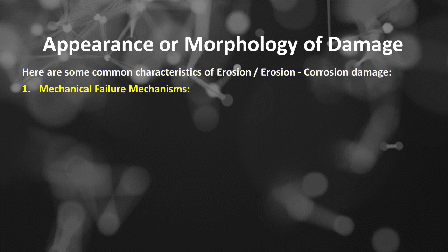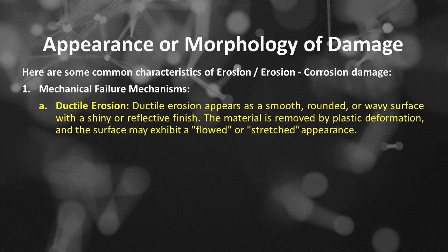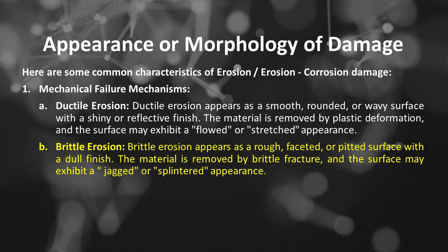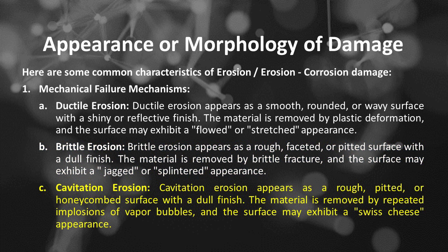Number 1 is mechanical failure mechanisms. The first is ductile erosion. Ductile erosion appears as a smooth, rounded, or wavy surface with a shiny or reflective finish. The material is removed by plastic deformation, and the surface may exhibit a flowed or stretched appearance. The second is brittle erosion. Brittle erosion appears as a rough, faceted, or pitted surface with a dull finish. The material is removed by brittle fracture, and the surface may exhibit a jagged or splintered appearance. The third is cavitation erosion. Cavitation erosion appears as a rough, pitted, or honeycombed surface with a dull finish. The material is removed by repeated implosions of vapor bubbles, and the surface may exhibit a Swiss cheese appearance.